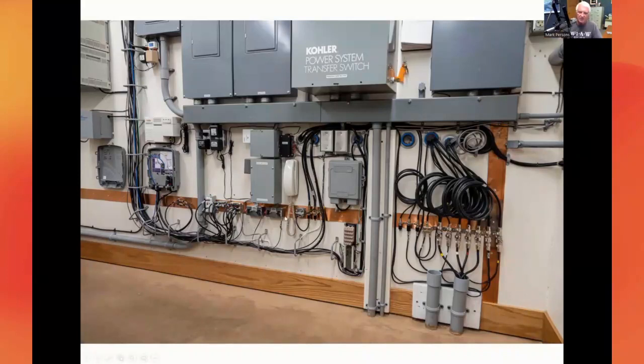But on the way, it picks up telephone, cable TV, you name it, and makes sure that their outer conductor is shunted. Any high voltages get shunted to this copper strap. It's also connected by this conduit to the city water pipe, which is copper in the basement.